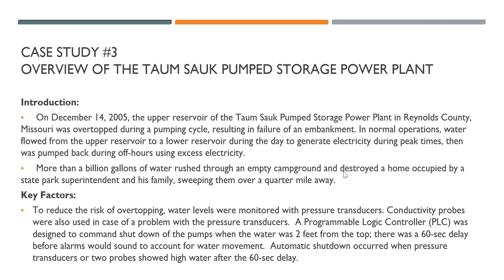So why did we get this accident? A couple of different reasons. First, it was found after the fact that the pressure transducer became detached and gave an erroneous reading. Also, one of the two conductivity probes was placed too high. So within the 60-second delay, the pumps were never shut down, and it was too late. The level of water got too high, and that led to the accident.